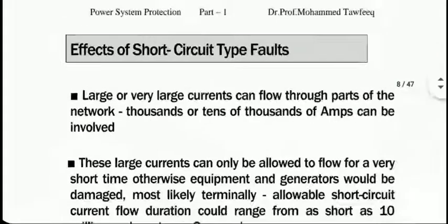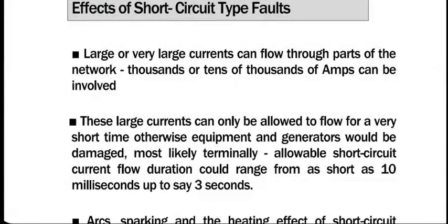Short circuit fault obviously will create large currents, which cannot be allowed to flow for more than a very small number of seconds, maybe even less than a second. Protection mechanism has to kick in within that period to prevent serious damage to equipment.